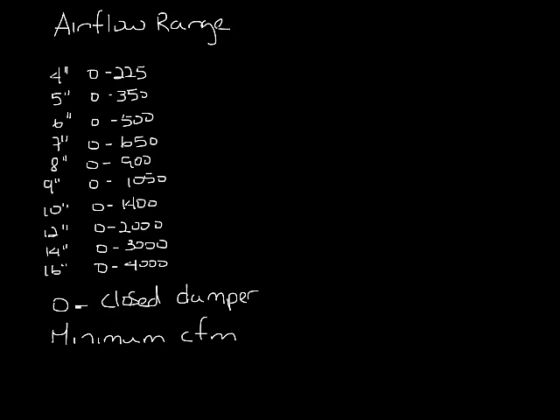So manufacturers publish minimum CFMs. Something to know about the minimum CFM of a VAV box is that it's all about what the VAV box controller can measure, not what the box itself can handle.